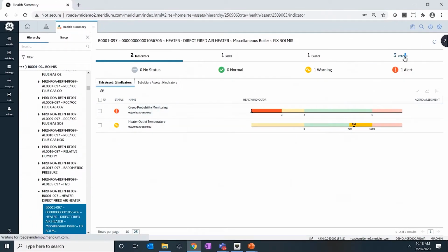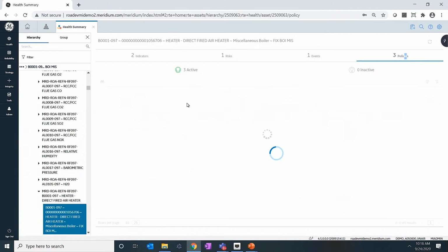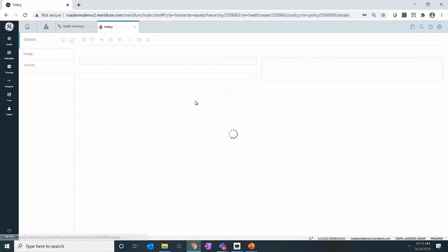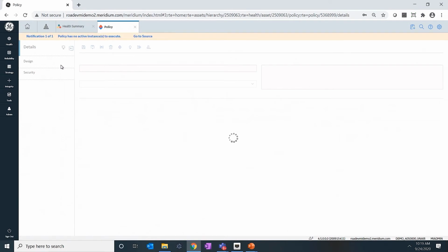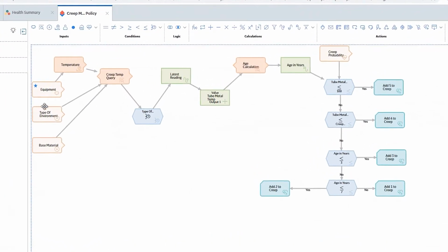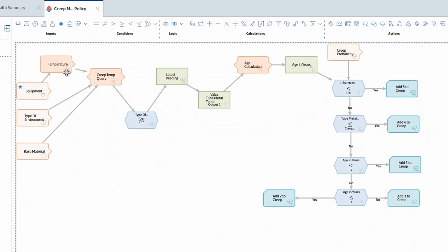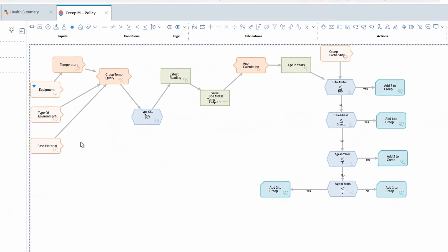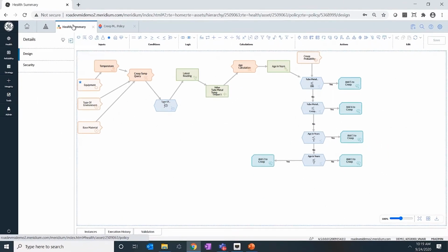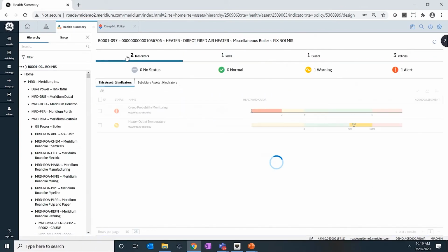And for doing that, we can use the Policy Designer to define your logic to calculate the creep probability of failure. So in this example, you can see that I have defined an entire policy which checks the temperature, compares it with the creep temperature based on the metallurgy, calculates the age, and then finally calculates the probability of failure.